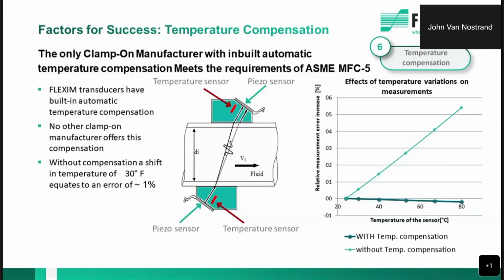FLEXIM uses an embedded RTD inside the transducer block, and this is an actual RTD, not a thermistor. It's not part of the measurement process. It's installed there to temperature compensate for what would show up as drift in the measurement from the temperature of the transducer blocks changing. Imagine if this transducer pair were mounted on a large pipe and one was facing the east and the other was facing west, rather than top and bottom. The sun comes up in the morning and it's beating down on the upstream transducer, and then as the day goes on, the sun goes to the other side of the pipe. On the west side of the pipe is the downstream. That change in temperature between those two transducers creates drift in the measurement. And FLEXIM has engineered the drift out of the measurement by adding that temperature compensation.